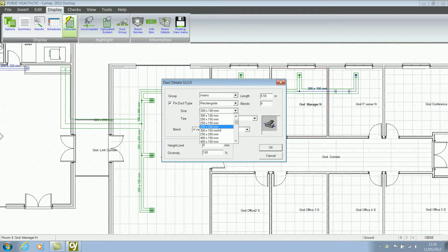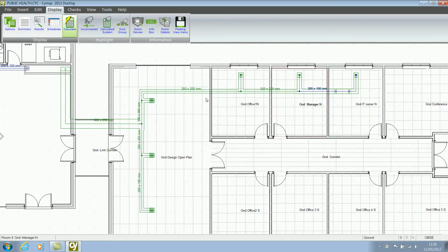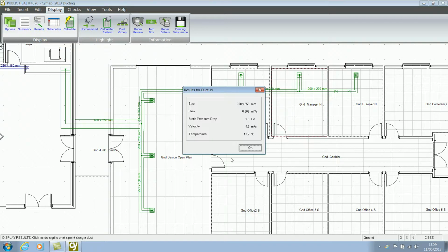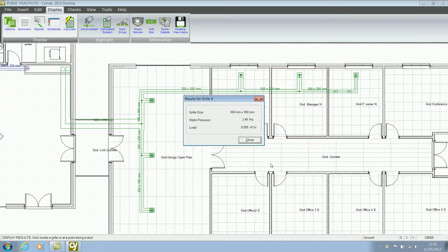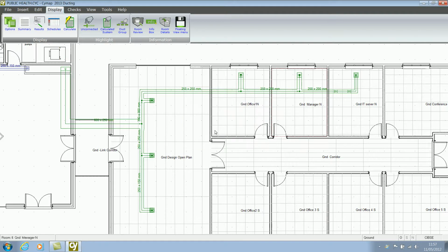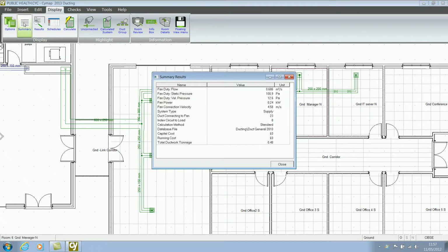If I want to maintain a different size, I can select the size, select OK, calculate again, and that will change the duct size. So the program is actually looking at the ceiling void restriction, looking at the centre line height of the ductwork, and will try and accommodate it if it can within the ceiling space. Again, we can look at the fan duty results for this system by selecting each piece of duct in turn, or we can look at the individual grills as well. And also we can look at the summary to give us the fan duty on the entire system and the index run.